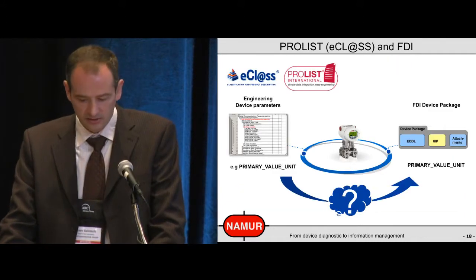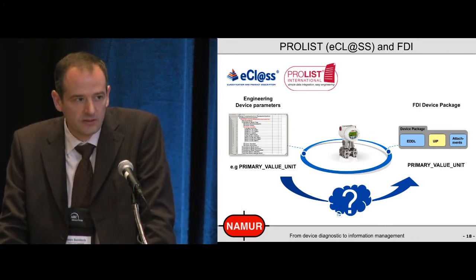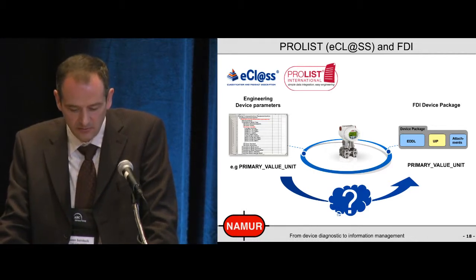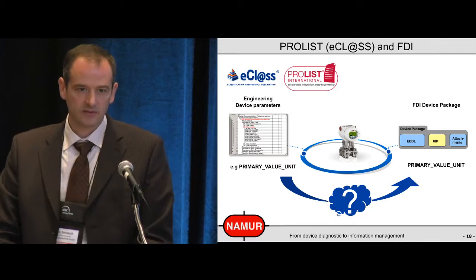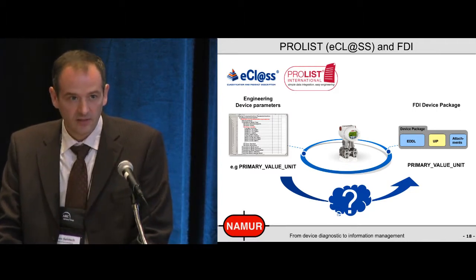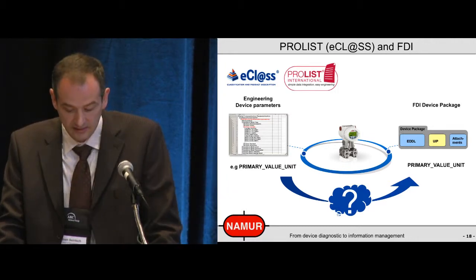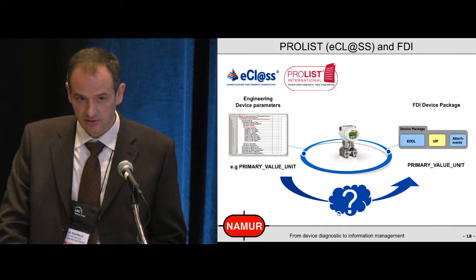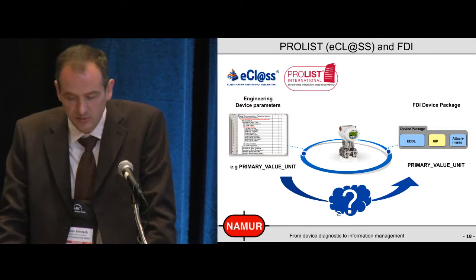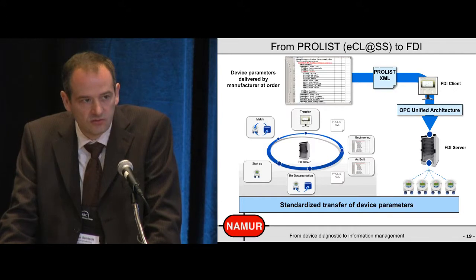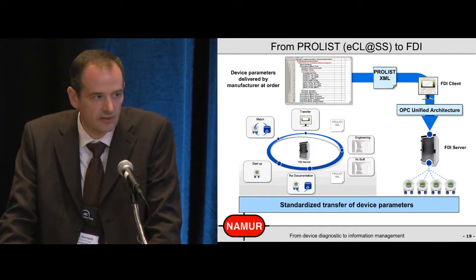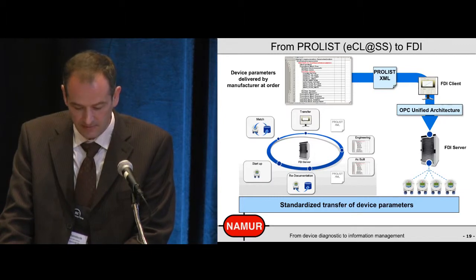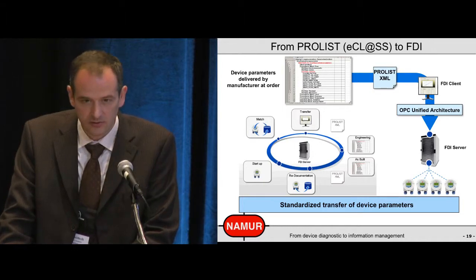Another feature is electronic data sheets — ECLASS ProLists — where you can use your preconfigured engineering parameters. You must bring them into the device. They are provided by the vendor on one side, and then you must transport them to the device package and afterwards into the device — that was very hard work to do by hand in the past. But with OPC UA it is possible to transfer the electronic data sheets directly via a ProList XML data sheet to an FDI client, and then through the OPC UA interface into the server and then into the device. So you have a fully automated engineering process, and that this really works will be demonstrated in March at a trade show in Düsseldorf.